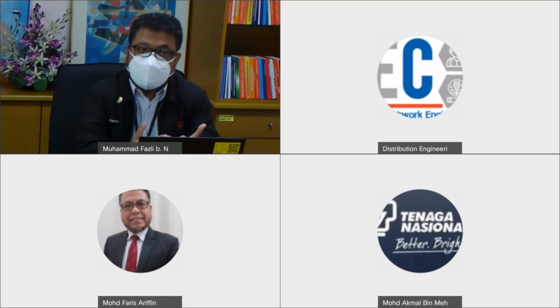So for the unshielded system, we need to deviate. We need to ensure that the lightning does not hit our conductor, because if it hits the conductor, it will do a lot of damage to our medium voltage overhead lines. So we need to make sure that the earth wire is properly installed. Secondly, we need to insulate. We have to make sure that the 170 kV minimum requirement is met.